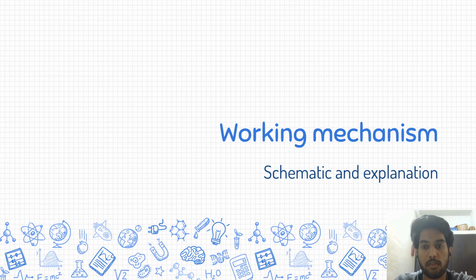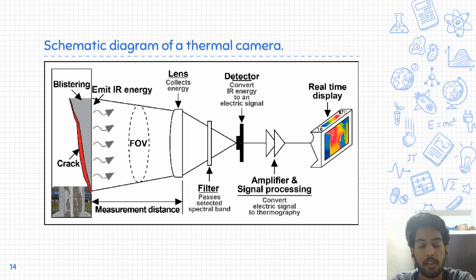Now let's take a look at a simple working mechanism through a schematic. So this is the schematic diagram of a thermal camera. As you can see, there is a source which emits infrared radiation in every direction. But whatever infrared energy is emitted that falls in the field of view of the lens is collected through the lens and it is focused onto the detector which is placed on the right side of the lens. But before it gets focused, it is filtered by a filter which passes selected spectral bands only. The IR radiation, after it falls over the detector, gets converted to an electrical signal. This electrical signal is amplified and processed by the inbuilt processors of the camera. Then these electrical signals are converted to a thermogram which is displayed in real time on the display of the camera.